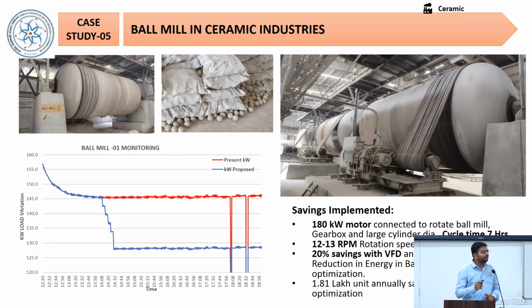We did not see any significant reduction in the ball mill rotation speed, and the industry doesn't require the torque that is initially required for the grinding action. After that, the slurry is prepared in a liquid form, so the industry doesn't require that much torque. After reducing the frequency throughout the cycle, this is the curve plotted, and the curve suggests that with the reduction in the frequency, we are getting good energy savings. About 5% energy savings were directly achieved during the audit.